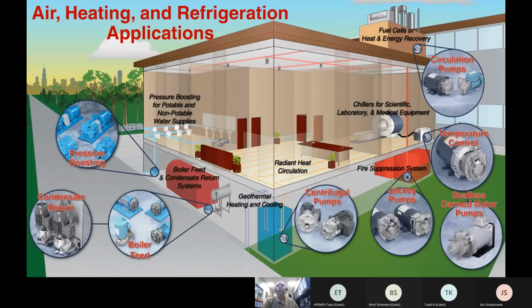We do a lot of circulating with the geothermal heating and cooling because you have hundreds or thousands of feet of piping underground. And when you get that much distance of piping, you need to be able to push water through that piping, and Regen turbines are great for that. In a closed loop system, a lot of times you can even do that with our centrifugal pumps, which also includes for radiated heat as well.